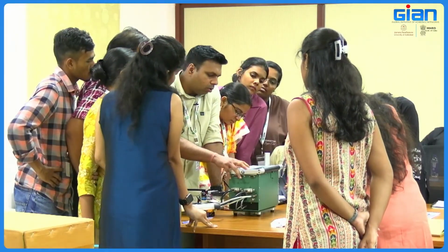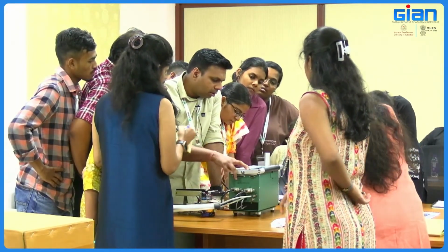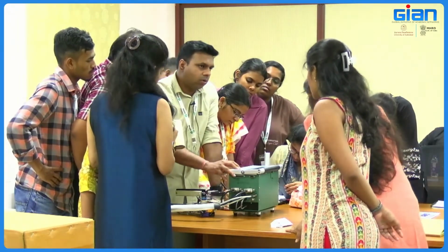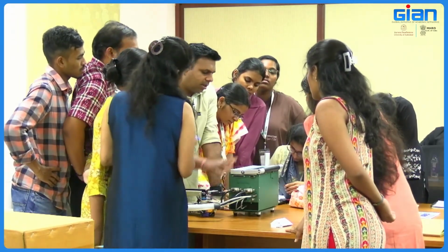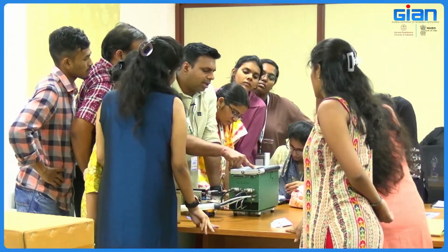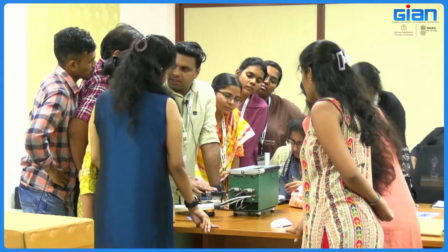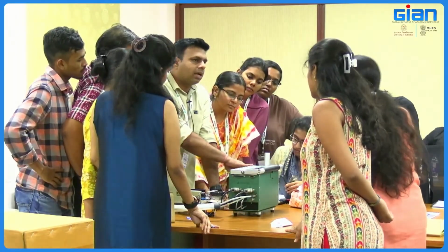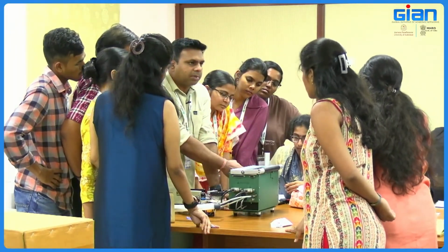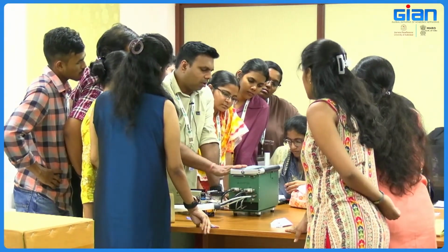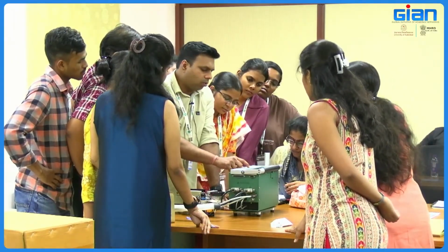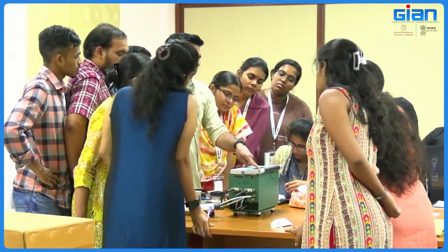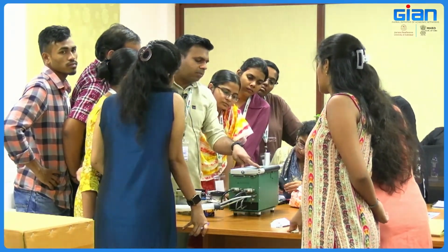Then you go to IRGA. Then press enter. And closed. Okay, and the total desiccant, it has been used 4 or 5 times, so it is fine. Now we have to press Y to continue. So then again it's asking that the chamber must be closed to 0 CO2.